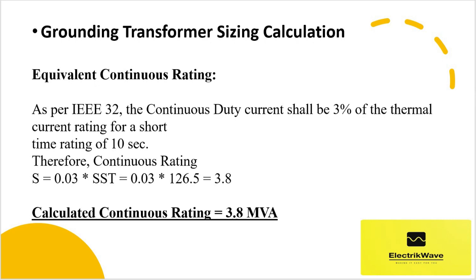As per IEEE 32, the continuous duty current shall be 3% of the thermal current rating for a short time rating of 10 seconds. Therefore, continuous rating S = 0.03 × Sst, which comes out to 3.8 MVA. Hence, the calculated continuous rating is 3.8 MVA.